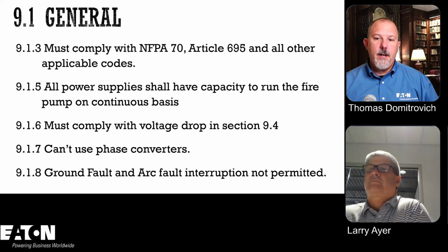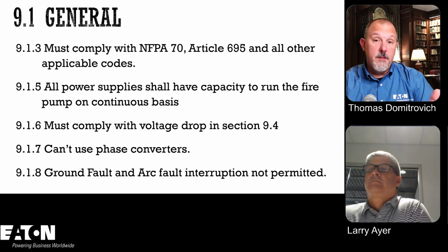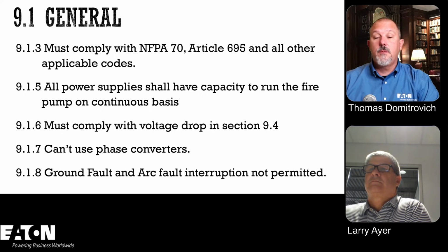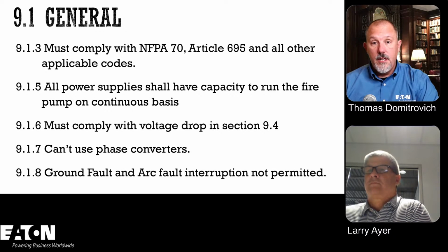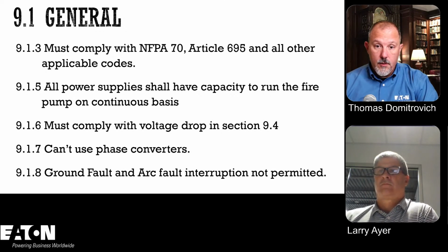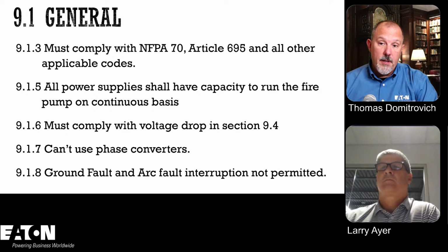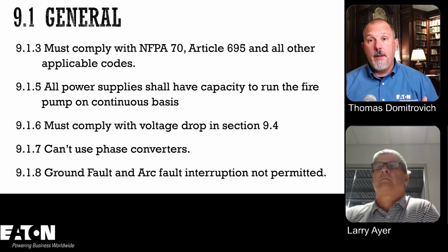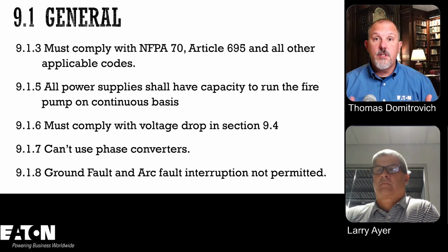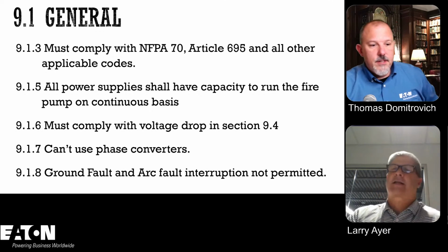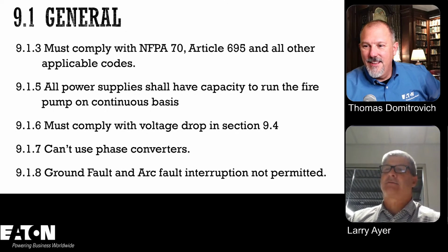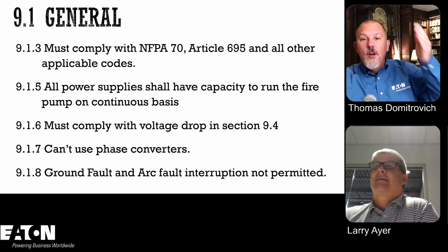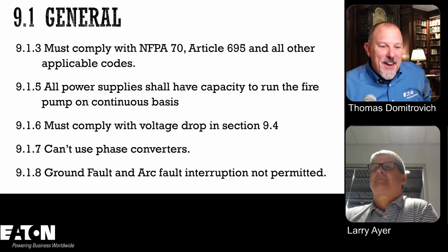There's a lot of, and I think in my humble opinion, because of all the advancements in arc reduction technologies, this probably deserves another look, because you probably can increase the reliability of your system if you can reduce the amount of damage that happens to equipment should a fault occur inside wherever, but that's neither here nor there. That sounds like that's coming from a guy that makes arc fault stuff. Yeah, it's coming from a manufacturer who wants to sell more arc flash reduction technologies in fire pump applications.